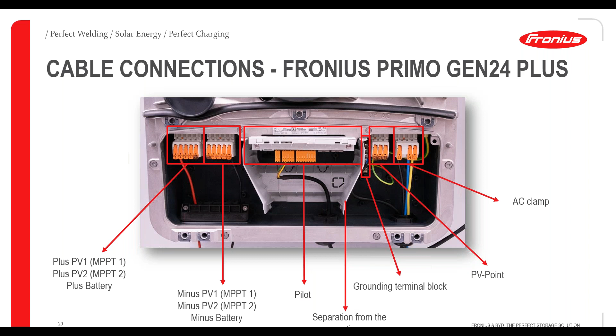On the left side is the DC connection for PV modules and batteries. In the middle of the connection area is the pilot, the new name for the communication card. On the right side you have the ground terminal block and the PV point mentioned earlier. We also connect the AC cables on the top right corner. There's also a removable separation in the middle that you can take out while connecting everything.